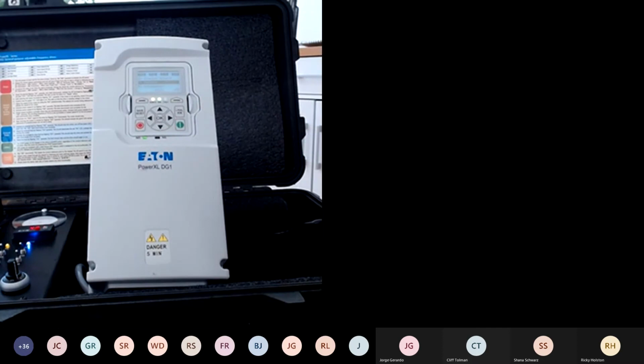So some of the neat things here is the switching frequency. If your noise on the drive is bothersome, you can change the switching frequency. And what that means is the number of those IGBT pulses on the output, the frequency of that can be reduced or increased to change the frequency.